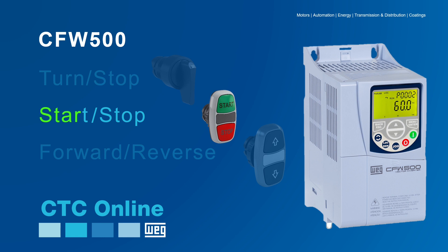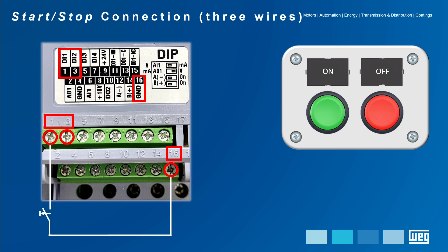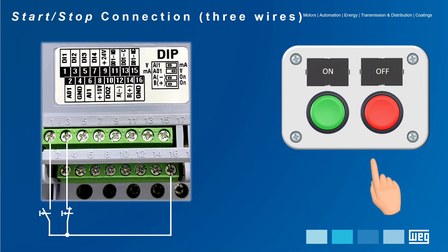The next command is the START STOP with three-wire connections. That setup uses a pulsating button where you can start and stop the motor without the need for an external contact for circuit interlock. In other words, you need two control signals connected to the digital inputs. In this example, digital input DI1 terminals 1 and 16 will receive the normally open contact signal from the ON button for the START function. Remember that the signals will be executed by PULSE commands on the PUSH buttons.